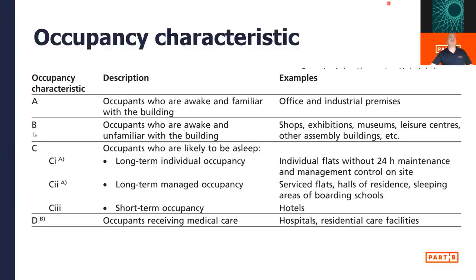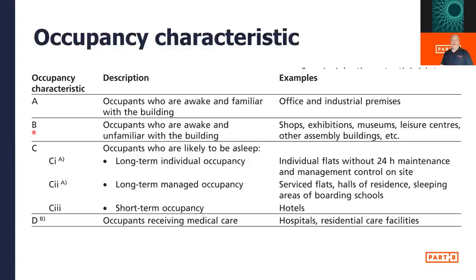Occupancy characteristic B — occupants who are also awake, but not so familiar. Examples are shops, exhibitions, museums, and leisure centres — places where members of the public gather in significant numbers. Yes, there will be employees there, but the vast majority are occupancy characteristic B. They're different from A because they're not trained or disciplined. You cannot train the public before they go into a shop or a theatre, so they don't know what to do in the event of a fire. Studies show people can hear a fire alarm going off and carry on with what they're doing unless somebody comes in and tells them it's time to move.